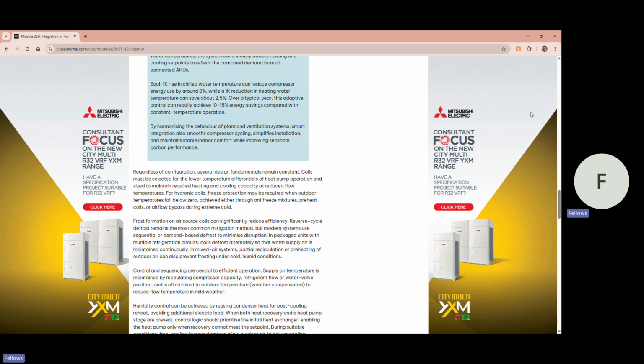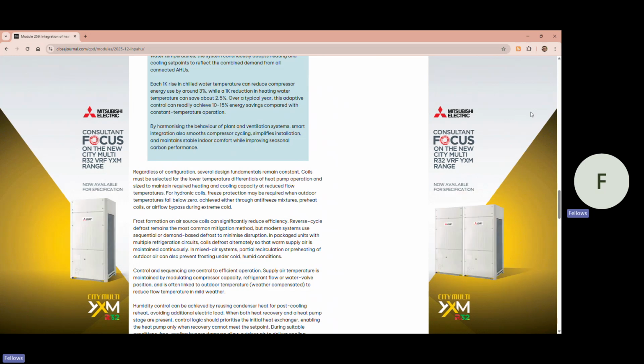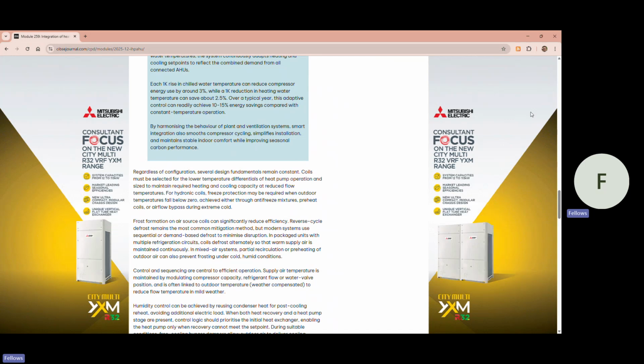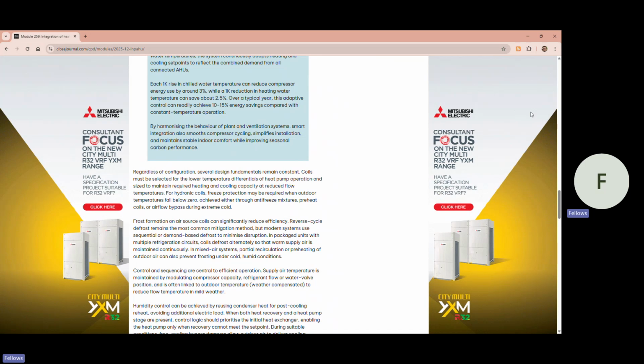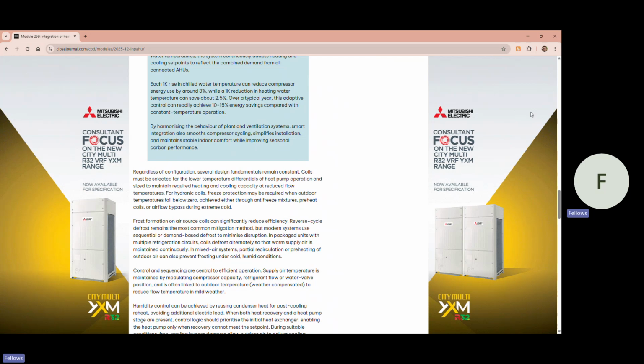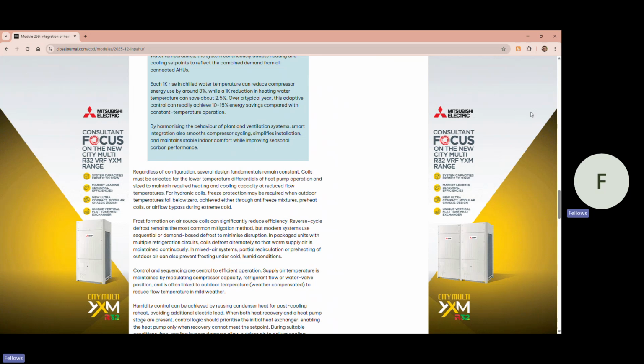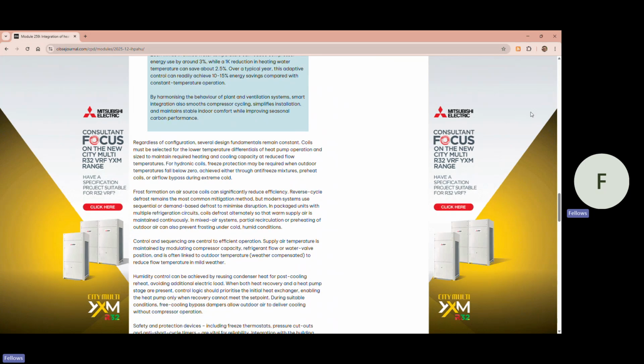Regardless of configuration, several design fundamentals remain constant. Coils must be selected for the lower temperature differentials of heat pump operation and sized to maintain required heating and cooling capacity at reduced flow temperatures. For hydronic coils, freeze protection may be required when outdoor temperatures fall below zero, achieved either through antifreeze mixtures, preheat coils, or airflow bypass during extreme cold.